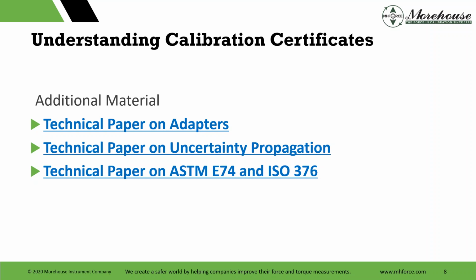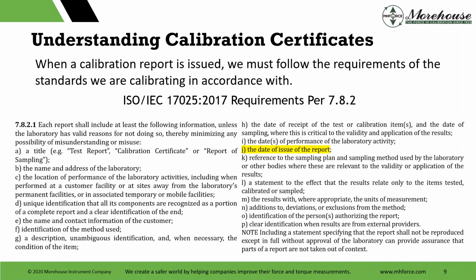Then we have a paper on uncertainty propagation. If you want to know how to do uncertainty propagation from dead weight the whole way down three tiers: a load cell calibrated in a dead weight machine, put in the cal machine to calibrate another cell, and then put that in another machine. And then we have a technical paper on ASTM E74 and ISO 376. They are not the same. So those are three maybe worthwhile reading materials that you have.